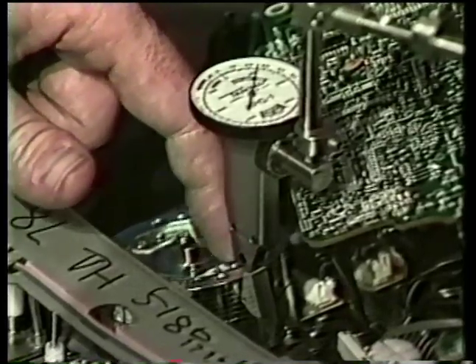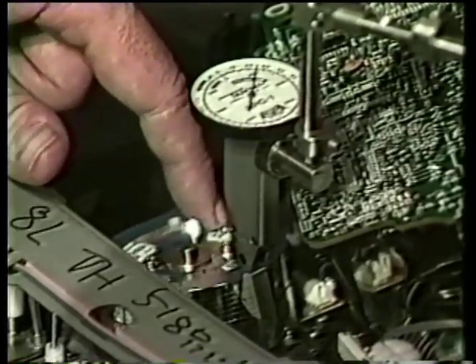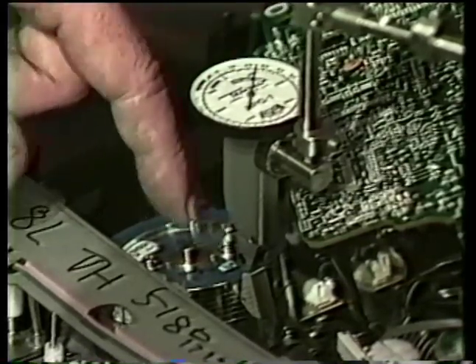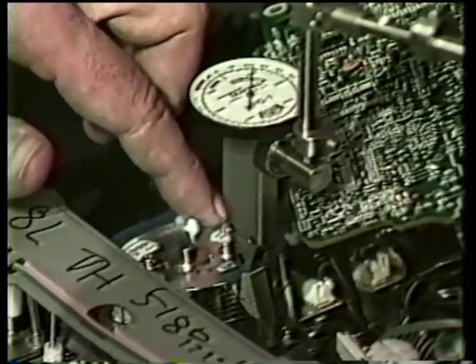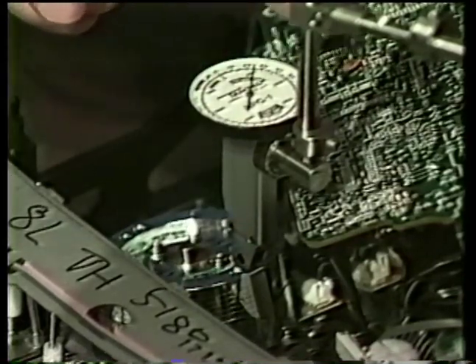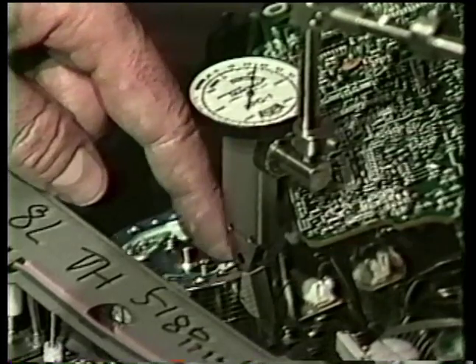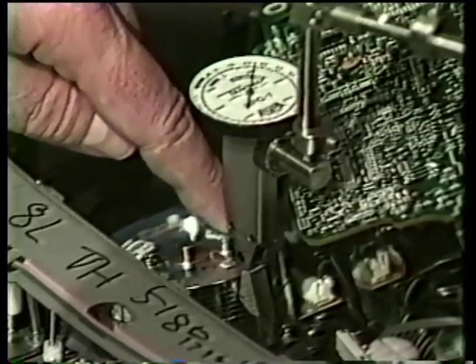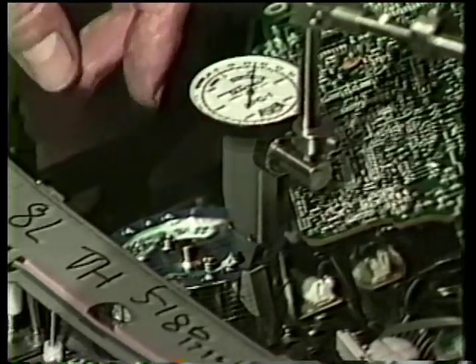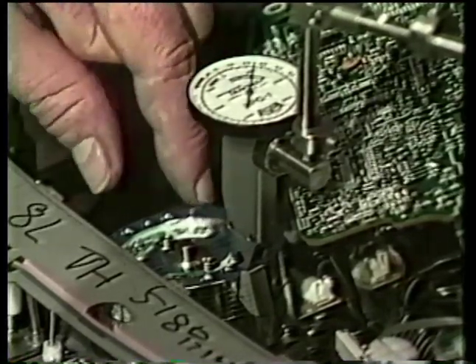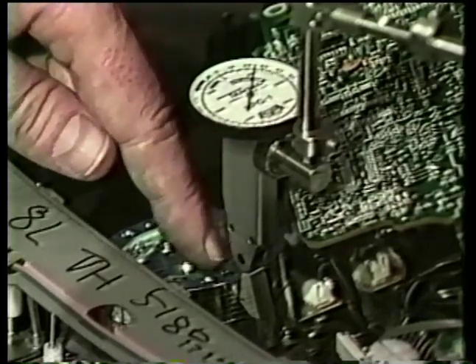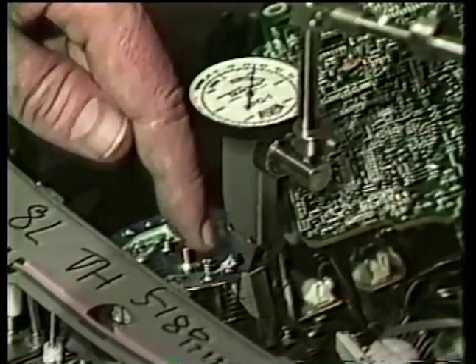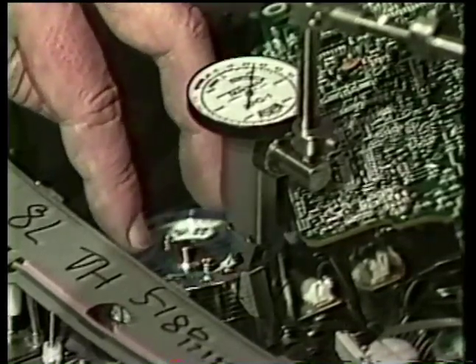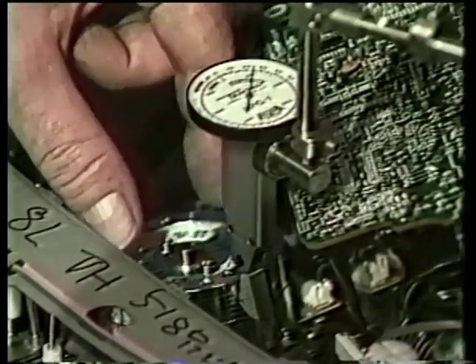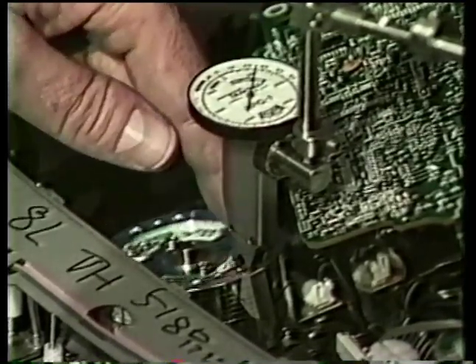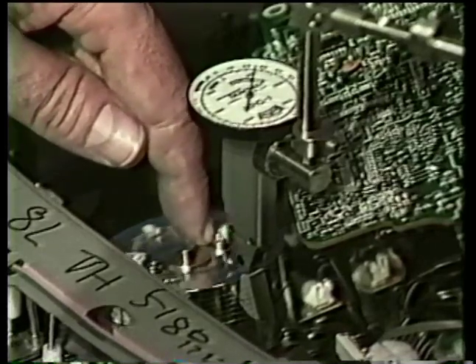noting any deviation in microns of the drum surface. If the drum is off center, I'm not sure how to simulate it, but the pointer would oscillate back and forth as you move the drum around. To correct those problems, different manufacturers have different ways, but basically what you need to do is take the part that reads the highest and position that under the foot, loosen the screws, move it over half that distance, and it's a lot harder than it sounds, believe me. Move it over half that distance when you retighten the screws. Check it again to make sure that it runs true.